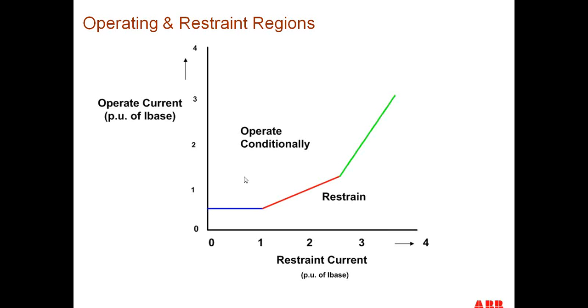It's based on the fact that all current transformers are not going to operate exactly the same. And the more current you put through the current transformer, the more likely you'll get some error current out of it. So in the first region, at very low current values, we feel that the current transformer would be performing very well. That's why we have a minimum IED current that it really operates for. That's like a half per unit.